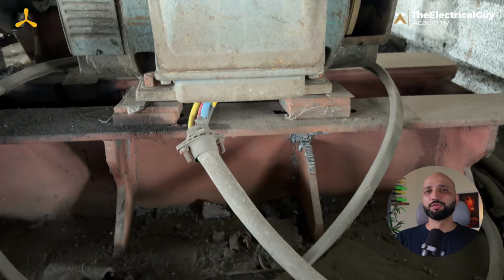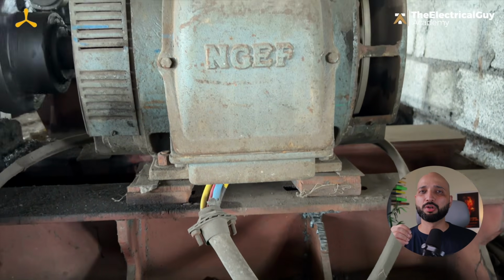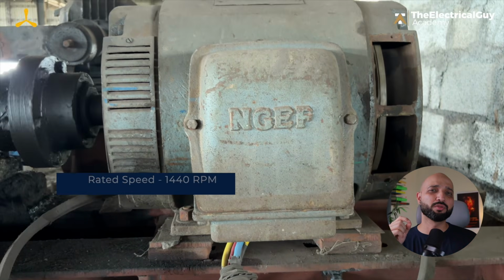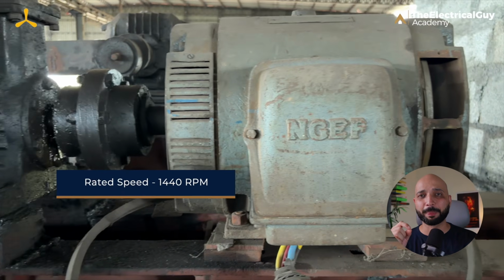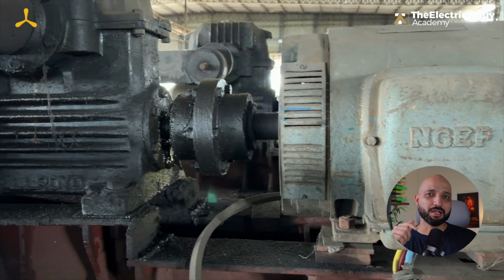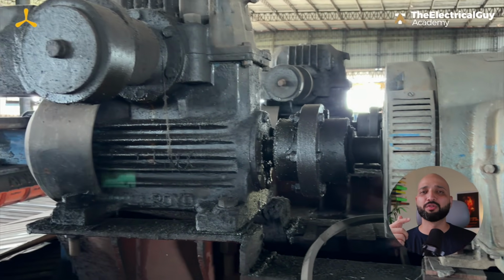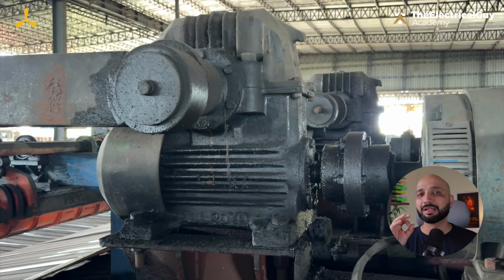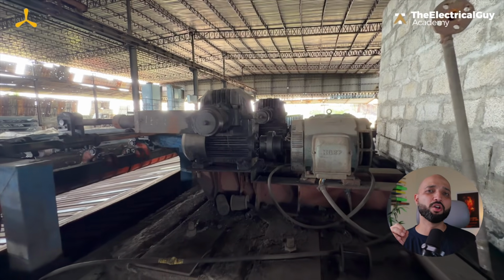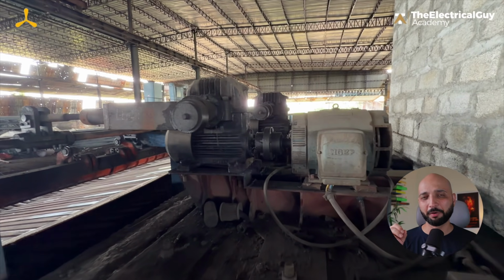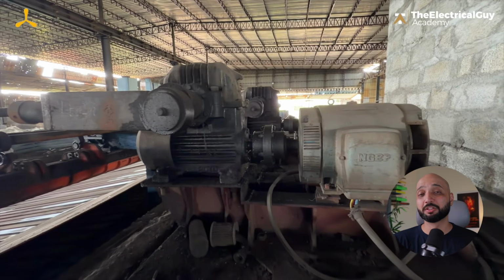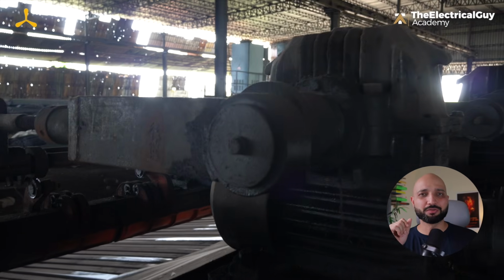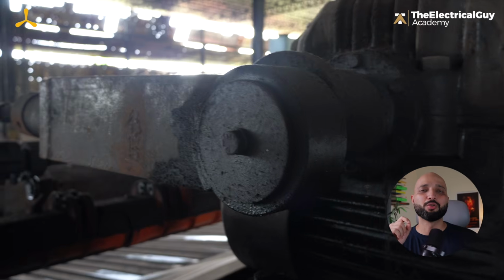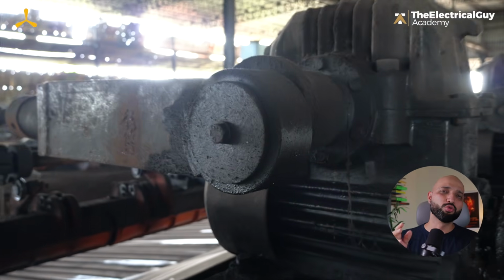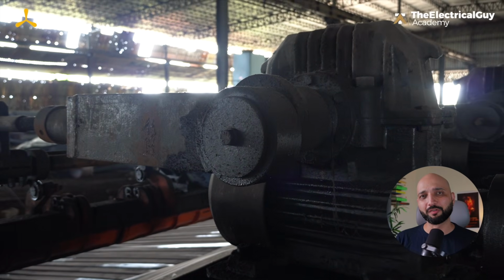Now, the motor that you see here is a squirrel cage induction motor with a rated speed of 1440 RPM. Now, here is the interesting part. The motor's rated speed is 1440 RPM, but the application demands a speed of only around 300 RPM. So how is this possible? Well, this is where the speed control comes into the picture. Now, let me show you the actual speed control panel of this motor.